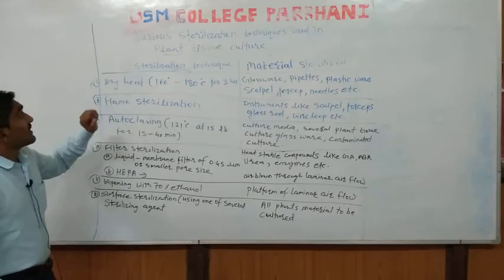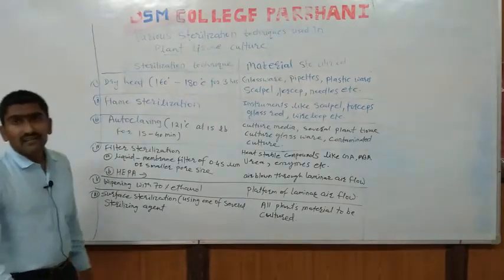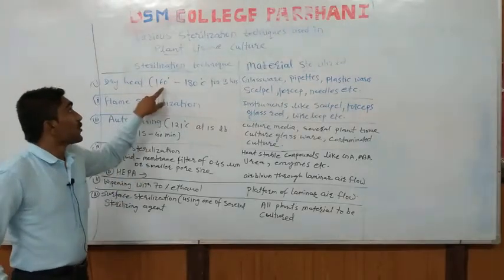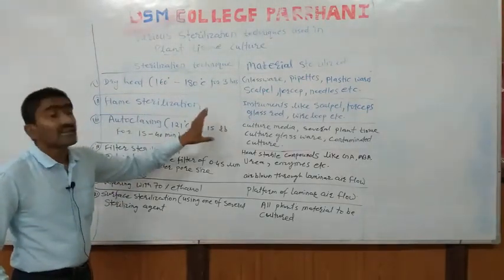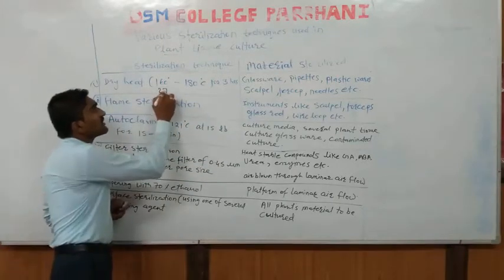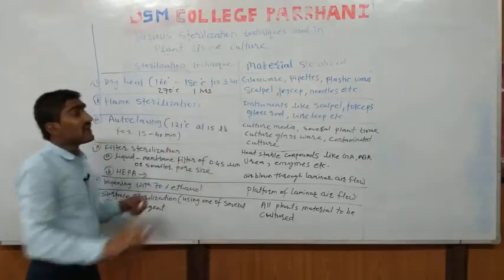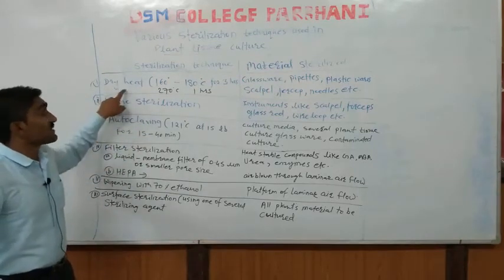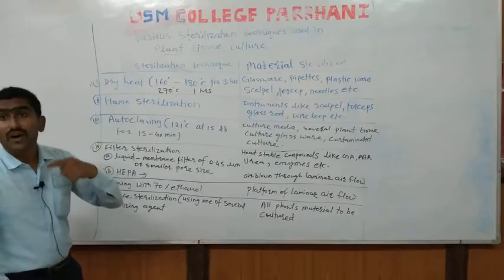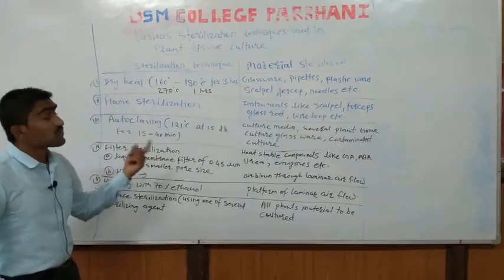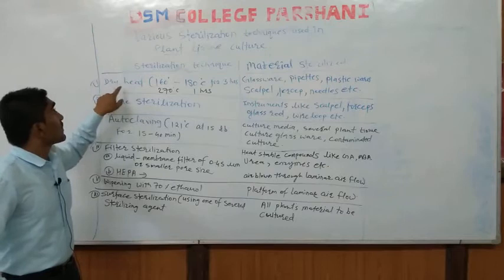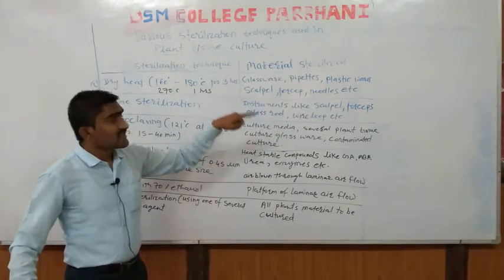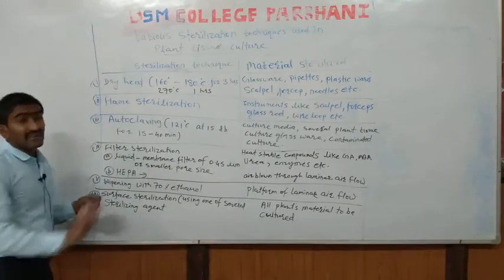Let us look at dry heat sterilization. For dry heat sterilization, a hot air oven is used. The principle involves keeping glassware at 160–180°C for 3 hours, or sometimes at 270°C for 1 hour — reducing the time by increasing the temperature. The dry heat is present inside the hot air oven. Materials that can be sterilized include glasswares, pipettes, plastic wares, scalpels, forceps, needles, etc.